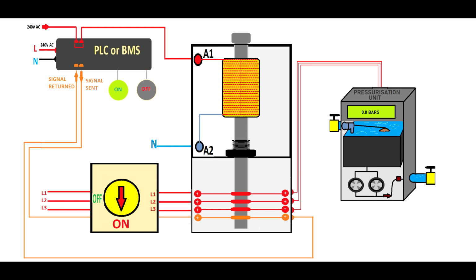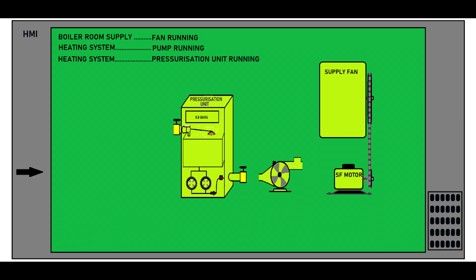The problem starts instead when we have a malfunction in the system and the circuit breakers are tripping. As you will see, as the PLC gets the information from a different power supply, it will still send the signal into the isolating switch and the contactor. So because of this situation, the engineer who is monitoring this system remotely will see on his display that the pressurization unit is healthy and working, despite it isn't.